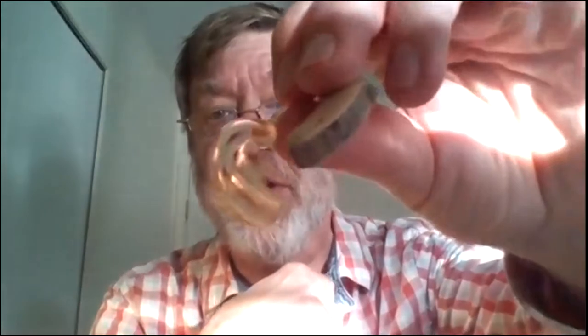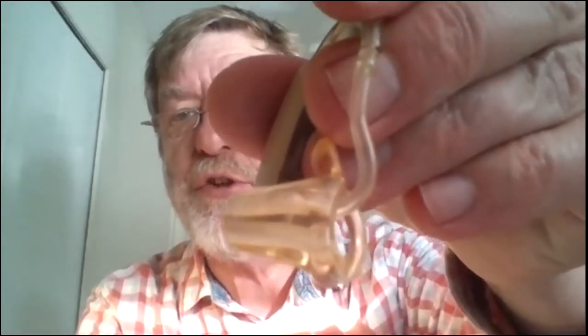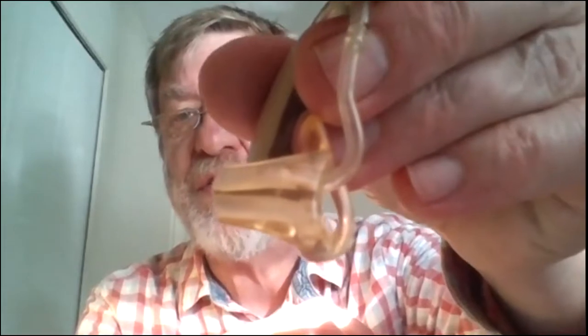Now, a lesser degree of hearing loss would be shown with a mold looking more like this, a lucite skeleton. And notice I can't bend it. It's hard. It's made of plexiglass. And it's got a vent in it. So if I hold this nice and close, you can see two pathways: one for the number 13 tubing and the other one as a vent.